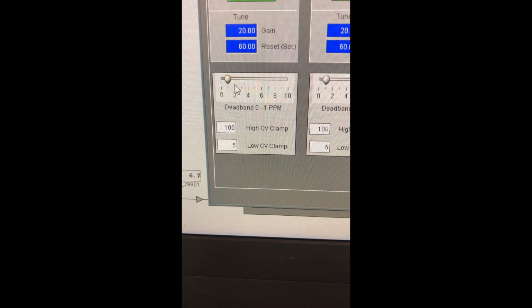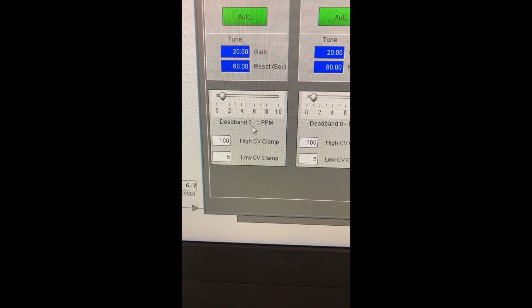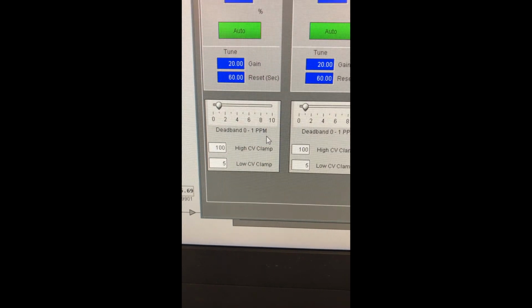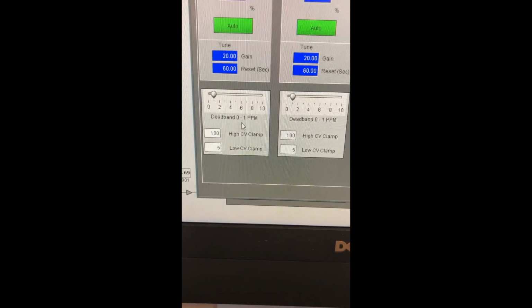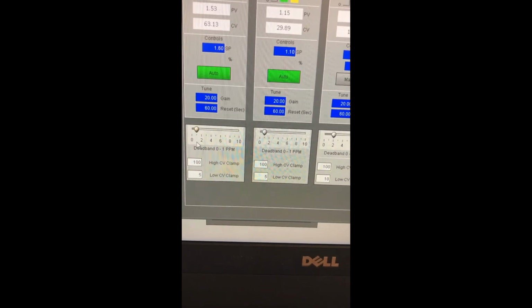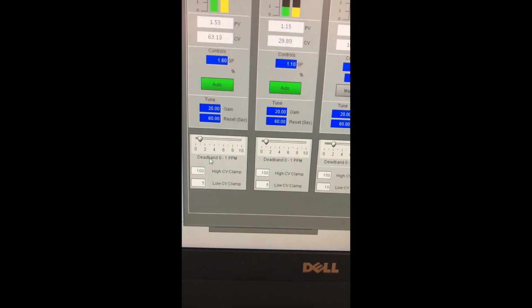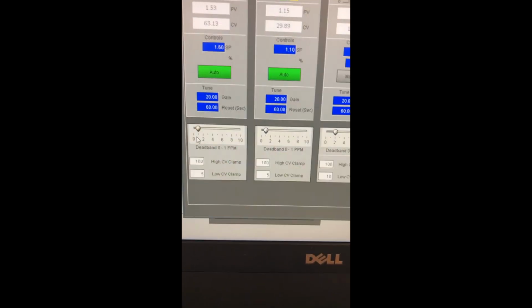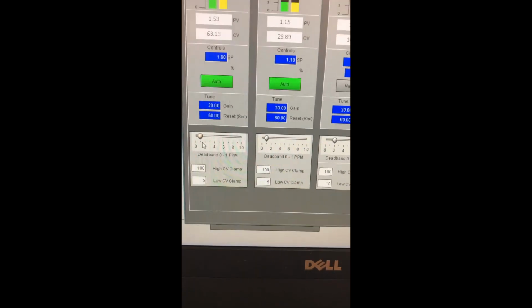I put these in recently here. This allows us to give some deadband between 0 and 1 part. There's no sense in having our actuators opening and closing all the time. If 0.1 ppm is good enough in terms of plus or minus for the DO, then this deadband will say, okay, if you're within 0.1 ppm, then we'll just leave you alone. If you get higher, plus or minus 0.1, then it's going to go ahead and operate the valve and try and correct it.